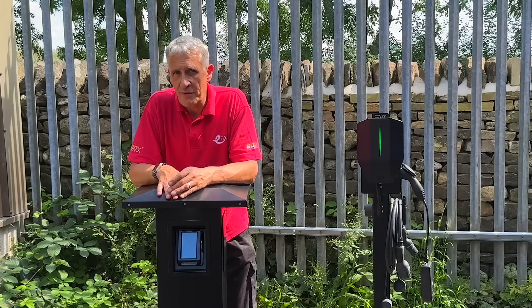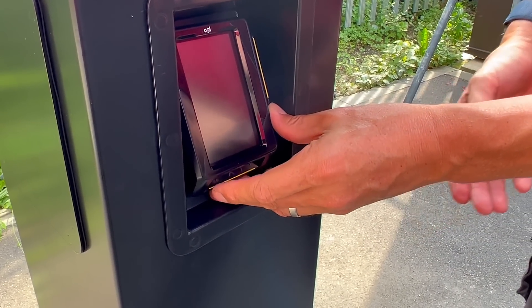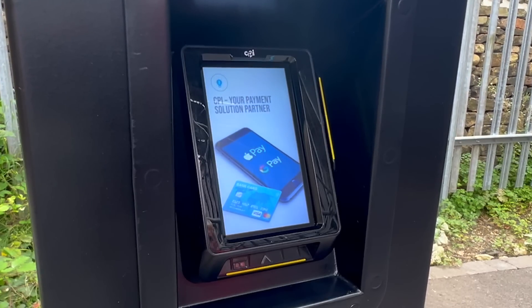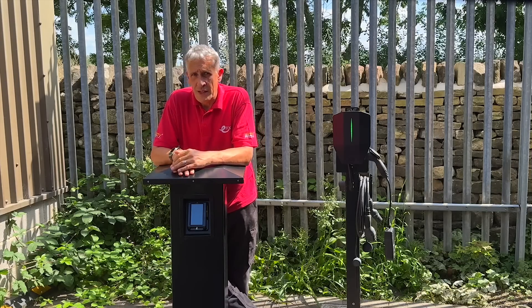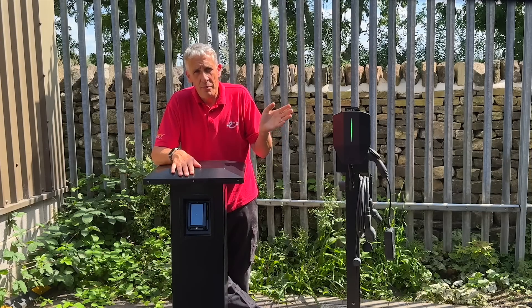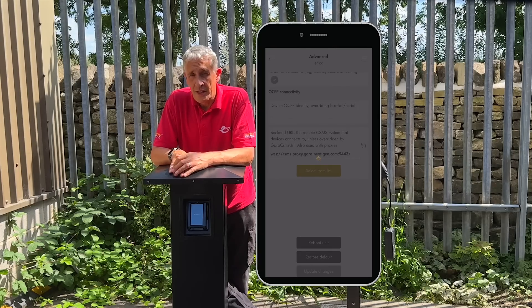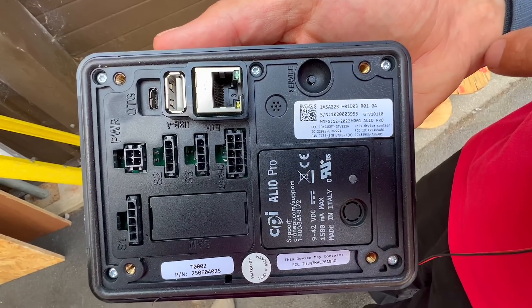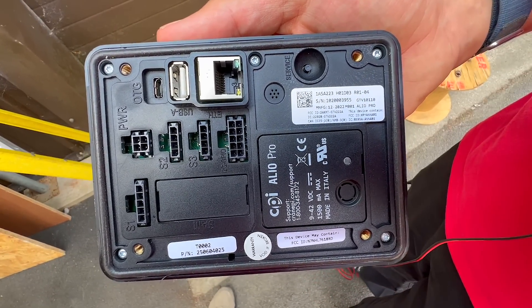So what's it like in practice? I've successfully installed the payment terminal into the EV Tower enclosure, connected the controller board, hooked up the ethernet connection, and powered it on — the physical installation is complete. I then updated the OCPP settings in the charger via the Garo app to redirect them to Clenergy and enabled app access. I also provided the charger ID from the app and the serial number of the payment terminal. From the installer's perspective, my work is now complete.